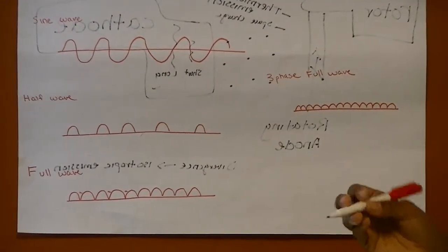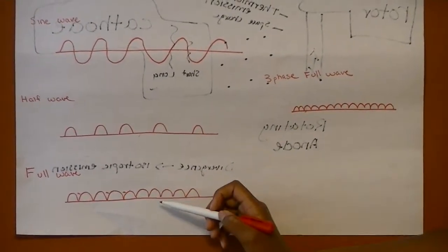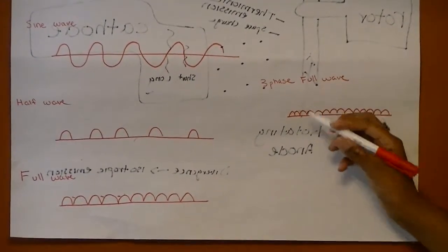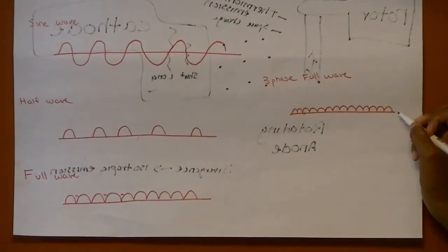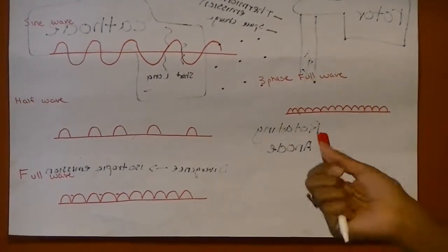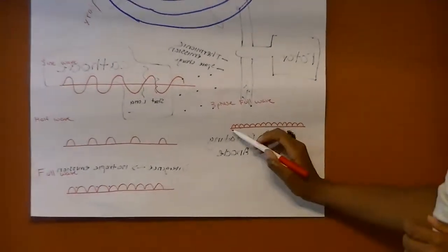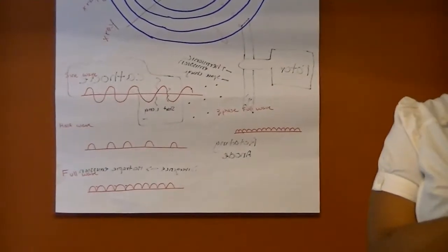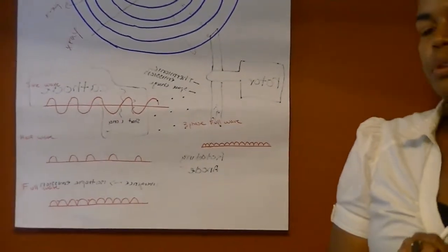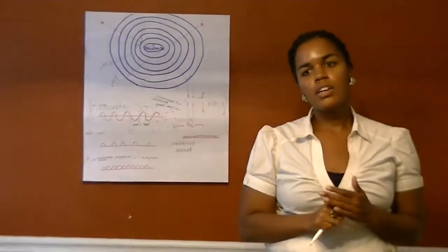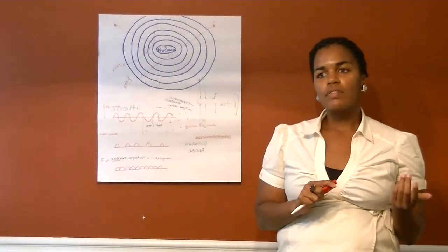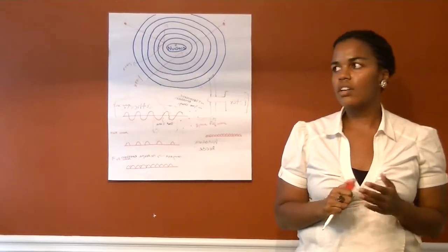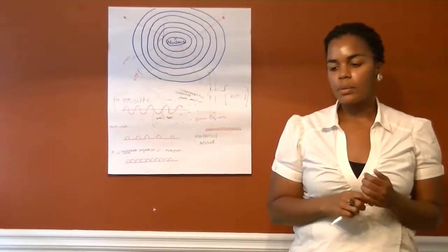During three-phase, what we're doing is we're combining 3 full sine waves, and here our graph becomes a little bit more condensed. So we have less space in between where we're producing X-rays. And the last one, I didn't draw it, but it's called high frequency. Basically, we're combining 3 waves and superimposing them on one another so that we have very little space in between where X-rays are produced. That's pretty much the best option for most chiropractic offices because you can plug that directly into the wall. It'll convert the 60 hertz to the 100 kilohertz current, and that's feasible for just a regular outlet plug.